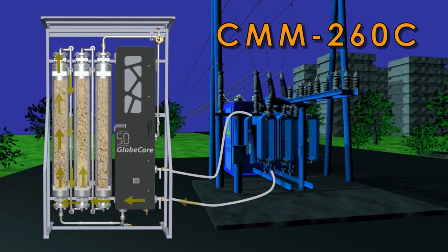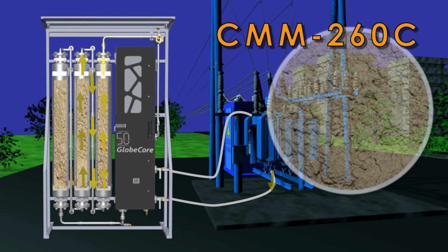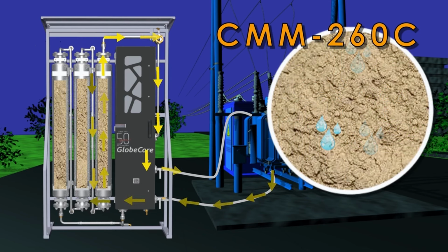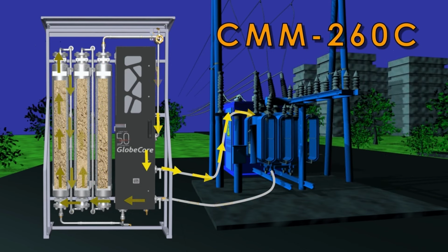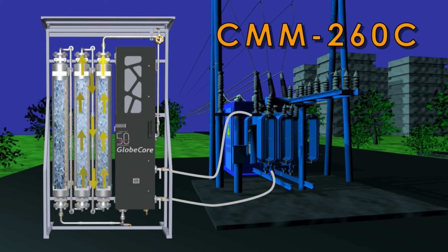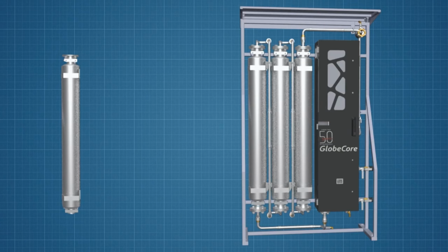A pump transports oil from the bottom of the transformer through 3 zeolite sorbent columns at a low rate. The zeolite absorbs water and captures it reliably in its granules. The dry oil goes back to the top of the transformer. It is possible to use another sorbent in lieu of zeolite in the columns. For example, if the oil requires not only drying, but also acidity reduction, silica gel can be used. The columns can be replaced after complete saturation of the sorbent. The columns are designed for easy replacement, and this operation requires one worker and takes 10 to 15 minutes.